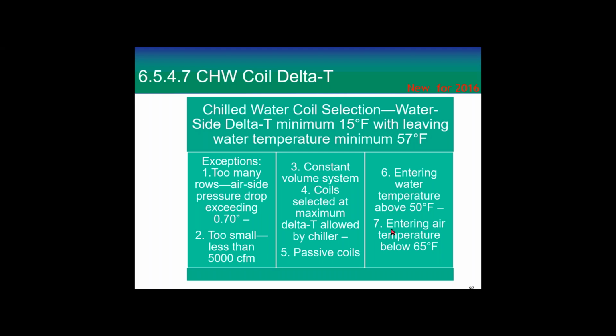15 from 57 is 42 degree water. So 42 degree water would be your coldest water you could supply. 42 degree water plus 15 is 57. If you use 44 degree water, you'd be fine. But if you use 41 degree water, you'd have to use 16 degree Delta T. Anyway, that's what we did. This was looking at the chillers, the cooling towers, the pumps, and the fans, and minimizing all those put together. We said 15 degrees was the right number to do that, or the minimum number to do that. You can go larger and probably maybe, but then your chiller may have to work harder.